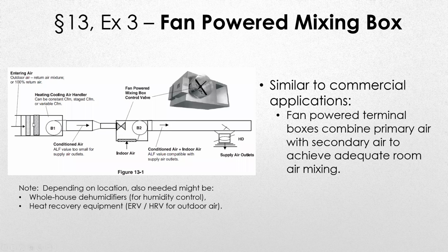This doesn't necessarily have to be one blower going into another blower. This system could be actually an air handler with a duct system, and then you come off at different points in the duct system to a fan-powered mixing box, which is what you would normally see in a commercial application like a school or a hospital type thing. And we know that this type of system does work. Whole house dehumidifier or heat recovery equipment may be required as well.